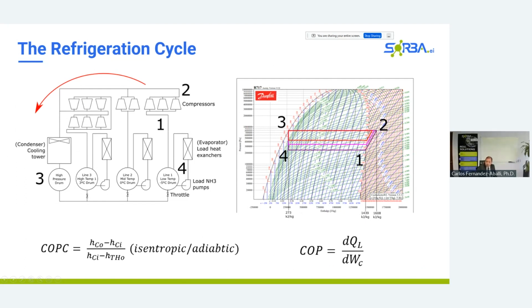Ideally, if the plant is correctly instrumented, or even better instrumented, we have temperature and pressure here, temperature and pressure here, and we have a good characterization of the loads. And in that case, we can measure electrical consumption during the compression. In that case, we can get a true COP of the system and use that as the optimization metric.